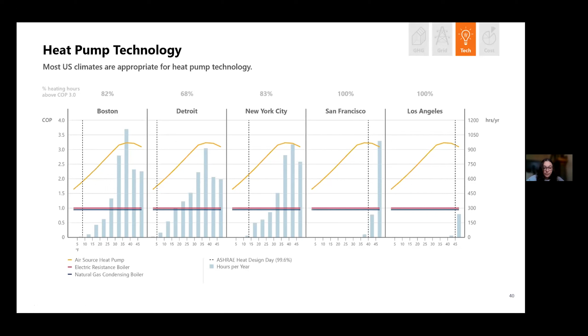Most importantly, our recommended option is a heat pump operating at a 3.0 COP—we'll talk about what it takes to get a heat pump to that level. The moral of the story is that as we reduce our energy dependency, we immediately reduce emissions below a fossil fuel condensing boiler baseline, getting our greenhouse gas emissions to zero faster than a condensing boiler ever could.